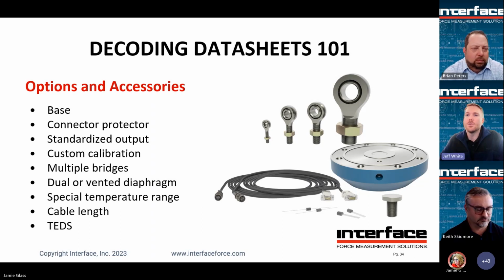Cable length, it's always a good thing to note how far the load cell will be from the instrument. We can make special cable lengths and a lot of times offer sense. So that would be your 6 wire, which will account for a potential drop in excitation voltage if you're running over a typical length. And then TEDS, if you need to swap load cells in and out frequently, this will allow for easy plug and play.